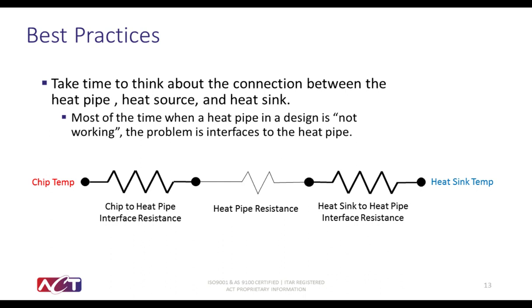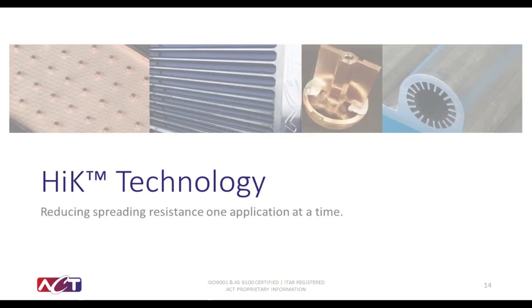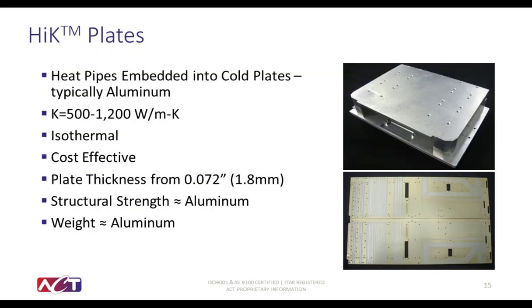So now that we've talked about that, I want to talk about the next logical step, which is taking that heat pipe and embedding it into your conduction plates, a next level solution. Heat pipes embedded into cold plates are referred to here at ACT as high K plates. This is where we take a traditional aluminum plate with a conductivity of about 200 watt per meter K, and we embed into it a heat pipe in a way that increases its thermal conductivity anywhere from 500 to 1200 watt per meter K. That range is so large due to the length of the heat pipe that potentially is inserted into that plate. The longer the heat pipe, the higher the effective conductivity is going to be within your plate. The benefit here is that you now have a plate made of aluminum embedded with heat pipes that still has the same weight of aluminum, the same structural strength as aluminum, but an exceedingly high thermal conductivity.